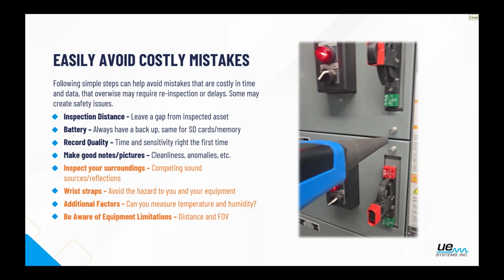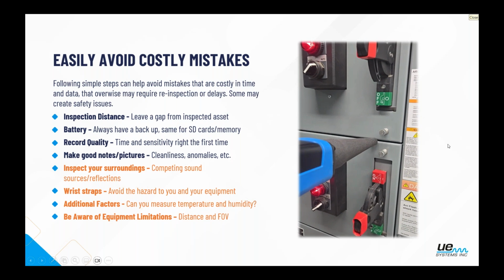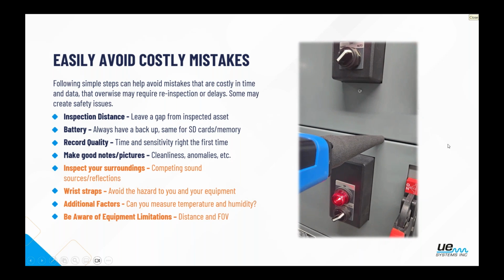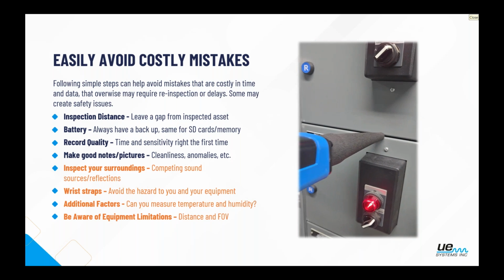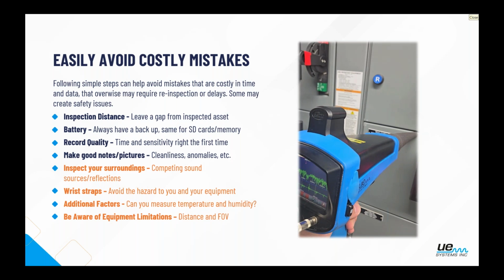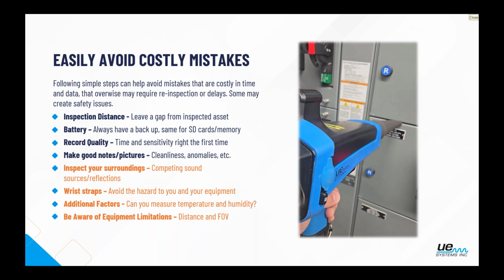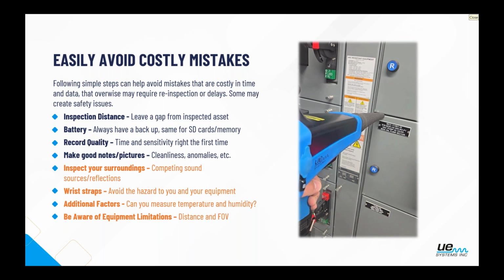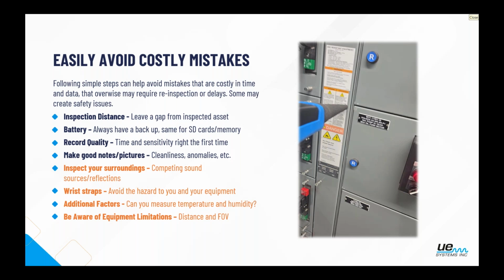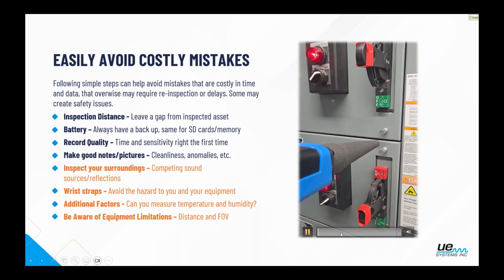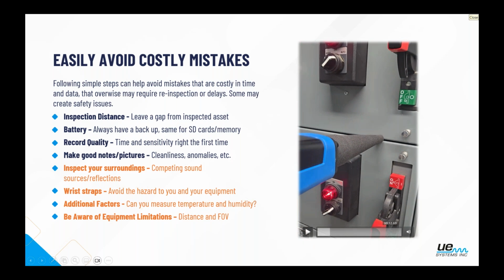It will always be tempting to get as close as possible because you're trying to hear what's going on inside there, but just leave a good 2 to 3 inch gap between the end of your device and whatever the seam is that you're inspecting. In this example that I'm going to play right now, unfortunately, I don't have a sound for this, but that is dragging all along the front of that cabinet. I'm making contact with something energized, which is in principle something I do not want to do at all.